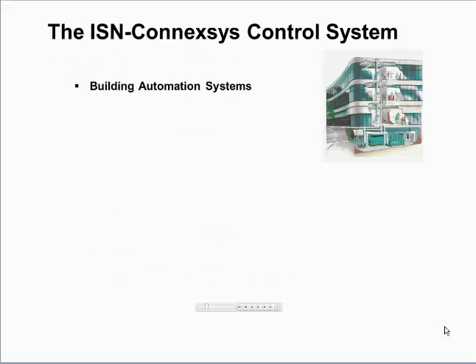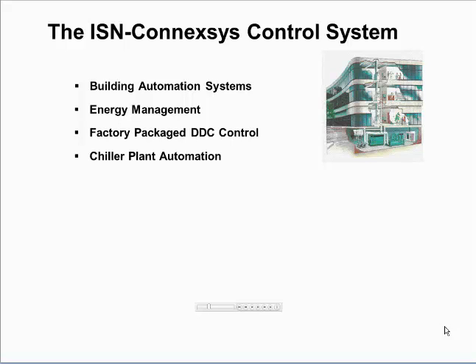The York ISN control system manages various building systems. It ensures the operational performance of the facility as well as the comfort and safety of building occupants. As an energy management system, it can monitor, measure, and control electrical building loads, like HVAC units and lighting systems across multiple locations. York ISN controllers can be used in a factory-assembled package of sensors, terminal units and heating controls. The ISN control system is used for chiller plant automation, to streamline plant operations and lower operating costs with control of chillers, VFDs, and pumps.